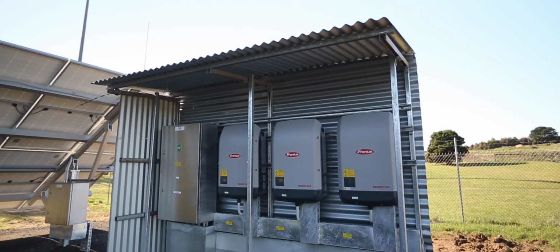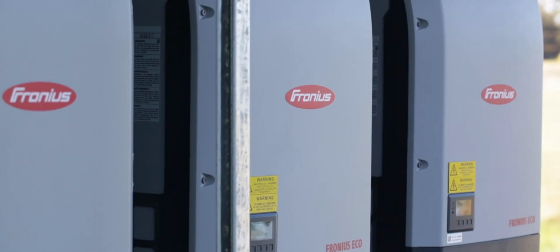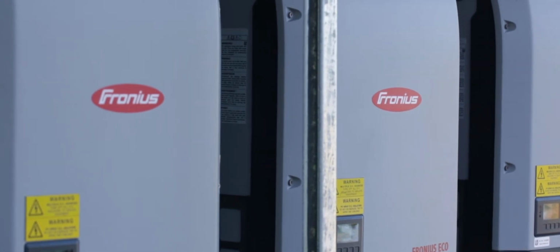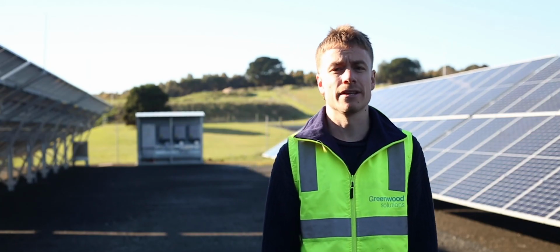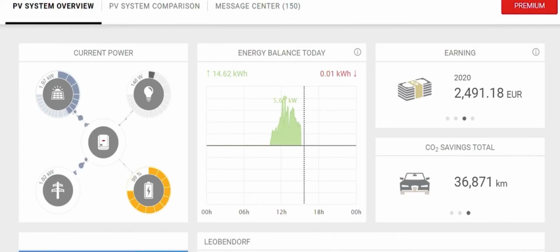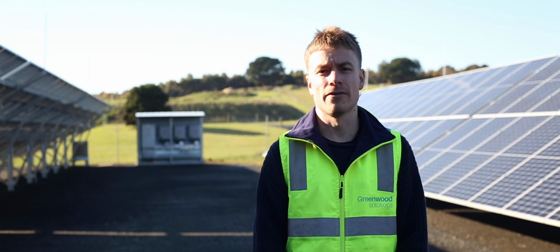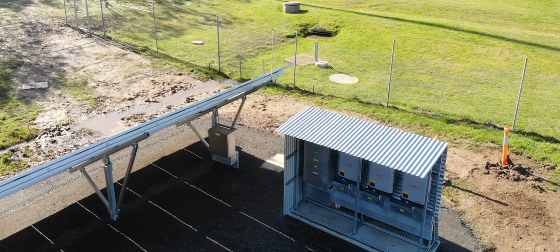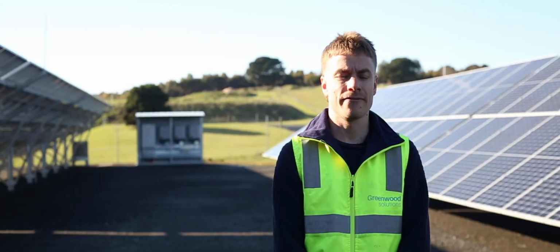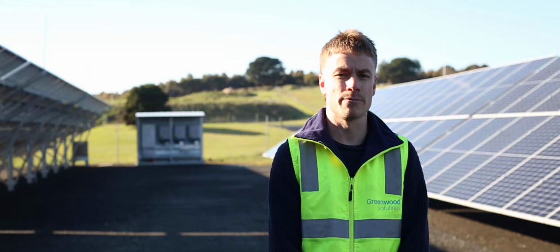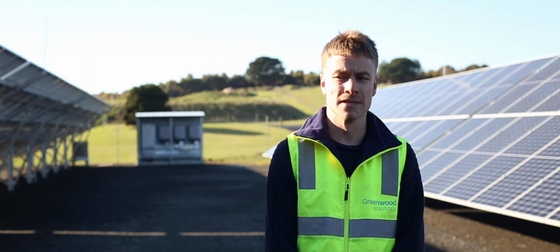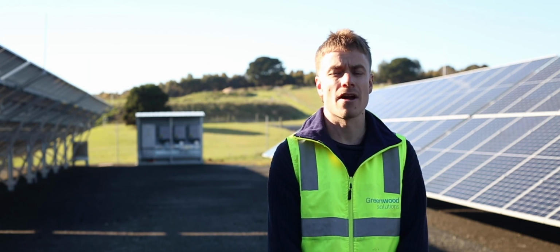On this project, we've used 3 Fronius Eco 27 inverters and a Fronius smart meter for the monitoring. These inverters were selected particularly because the other sites are already using Fronius, so we wanted to keep their monitoring platform on one portal, and also the reliability for Fronius being an industry leader had a big say in that decision as well. And the inverters were positioned at the array for serviceability. There was also a particular challenge on this project of where we could put them due to the underground service location, so we had to put them between the arrays and minimise the amount of effect any potential shading could have on the array.